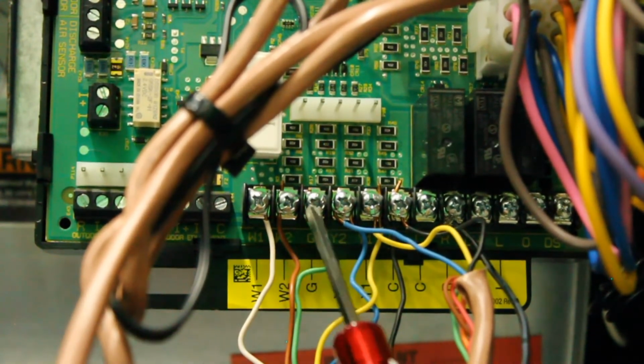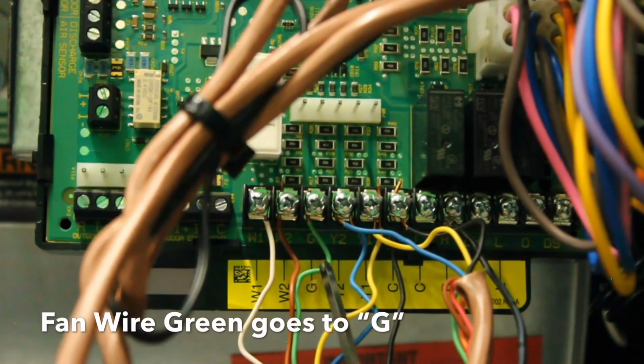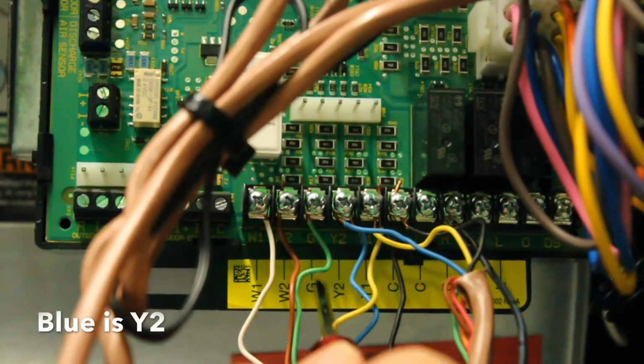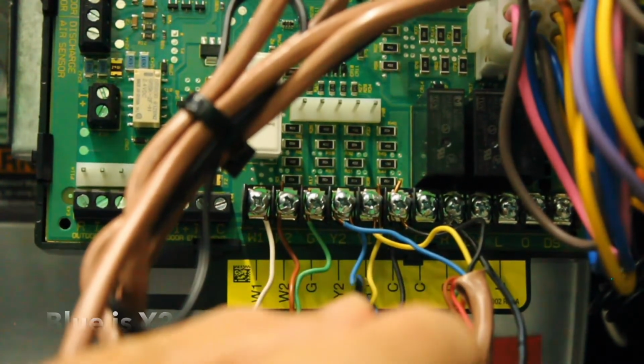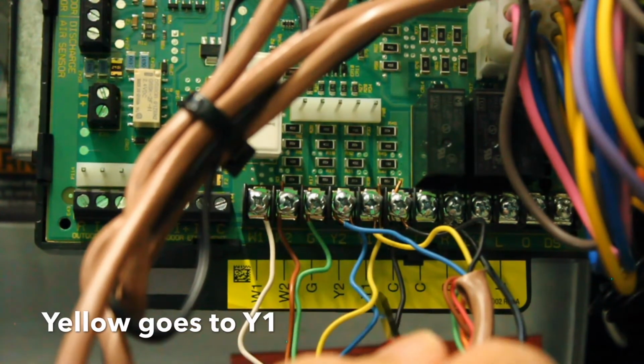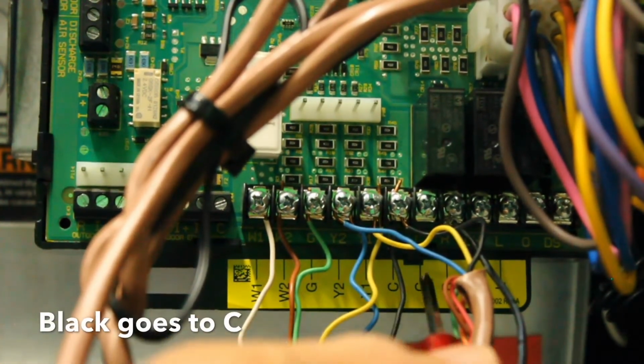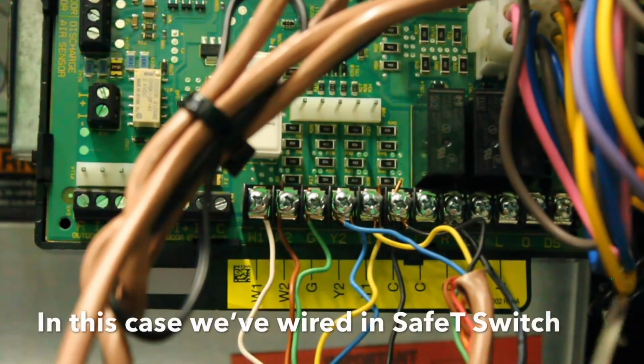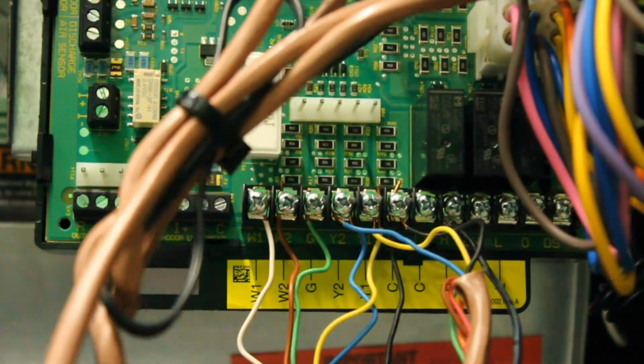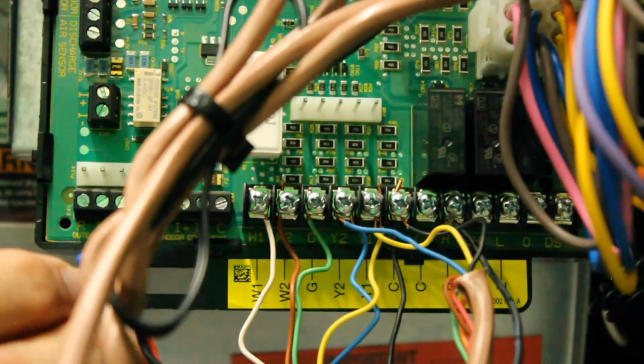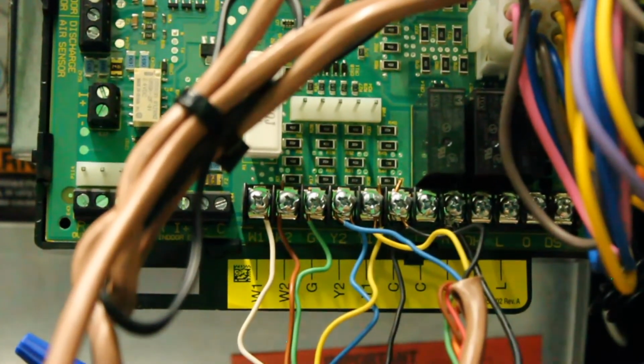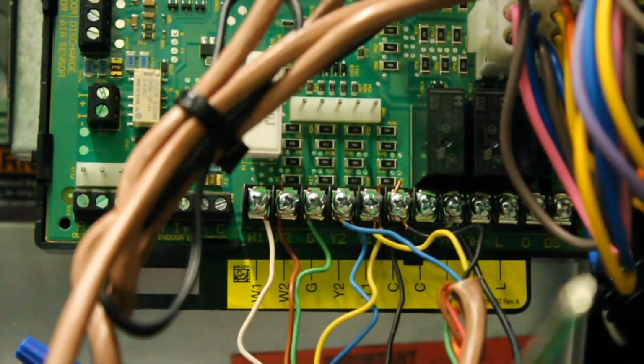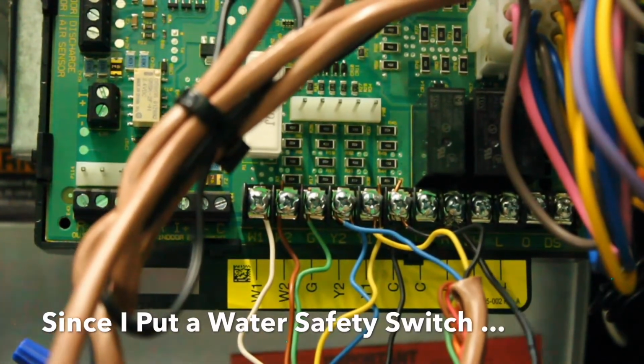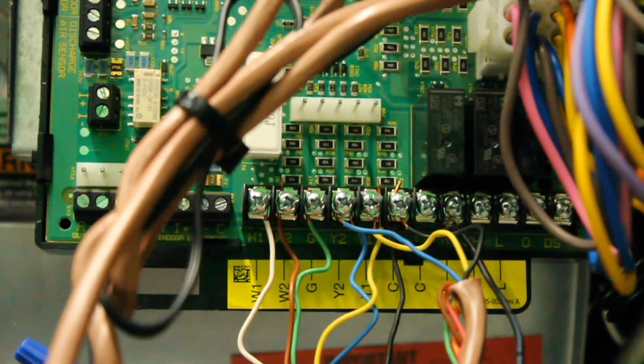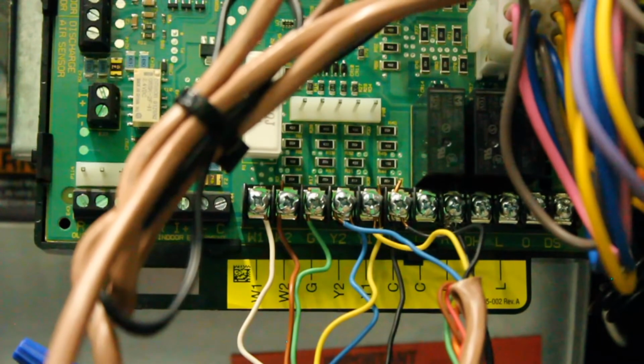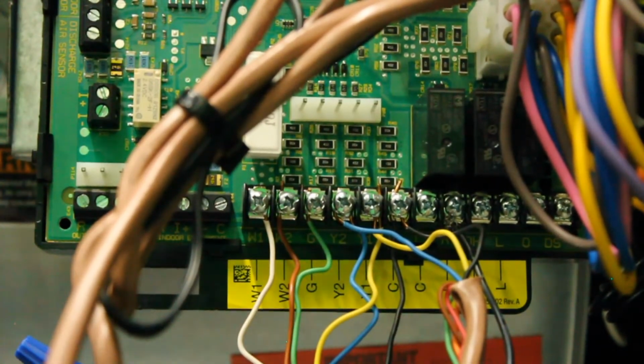The third wire on the board is the fan wire, the green, which is going to go to G on the board. And the blue wire goes to Y2. My yellow wire goes to Y1. My black wire is going to C. In this case, I do have a safety protection on this unit, which is these 2 black wires. My red wire, if we follow the black wire out, it goes to R. My red wire is normally connected to R, but since I put a float and safety or water safety switch so my place doesn't get filled with water if the drain blocks, I added an extra protection. If the safety switch opens, my unit stops and I don't flood the place out.